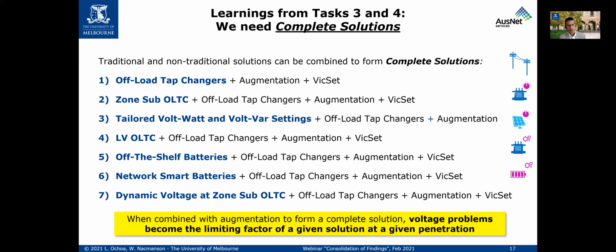Playing with the zone substation OLTC, changing the target - for instance from 1 per unit to 0.98, lowering the voltages all the time - can be effective to some extent, but it also has limitations.